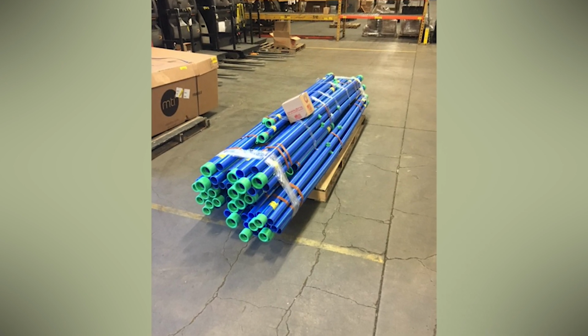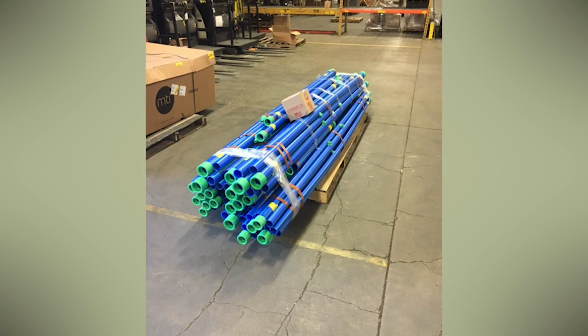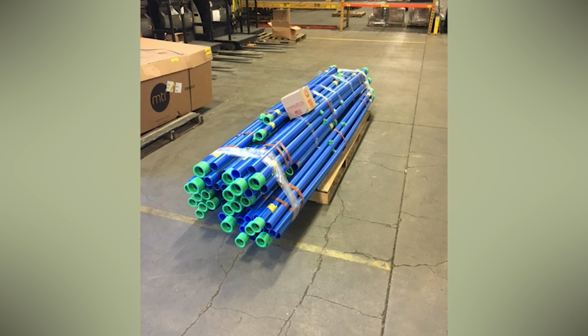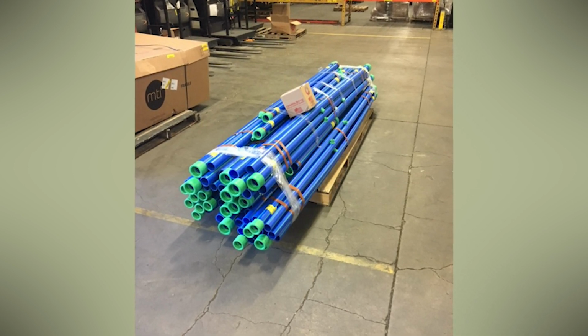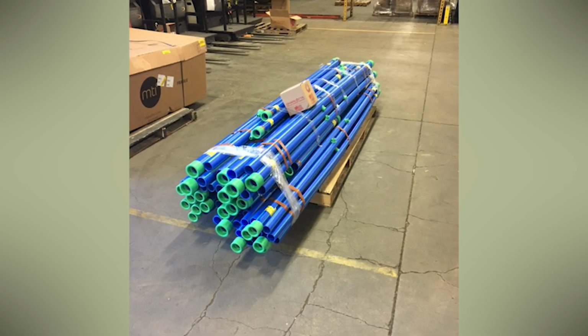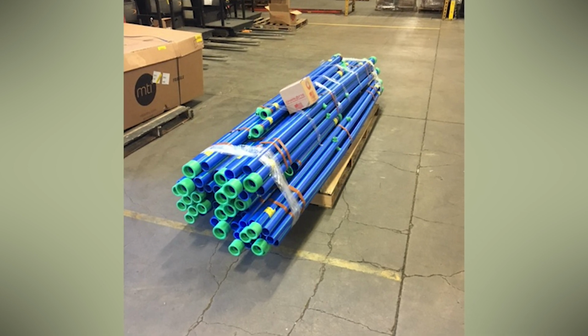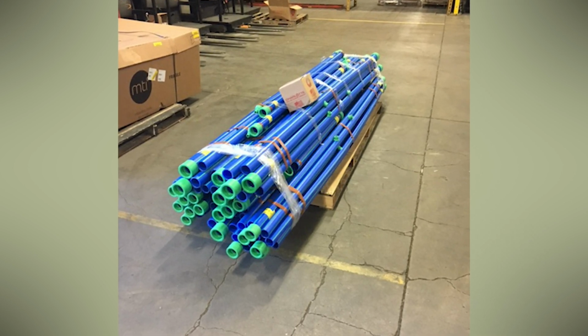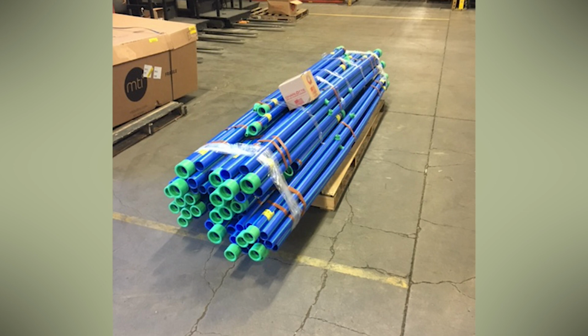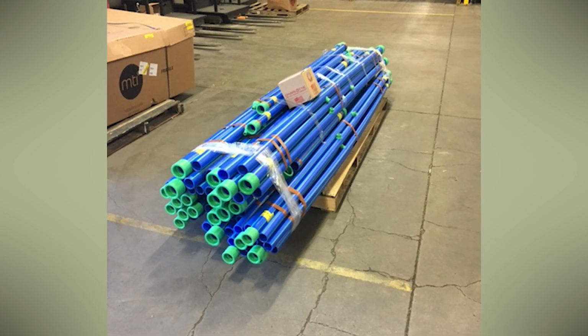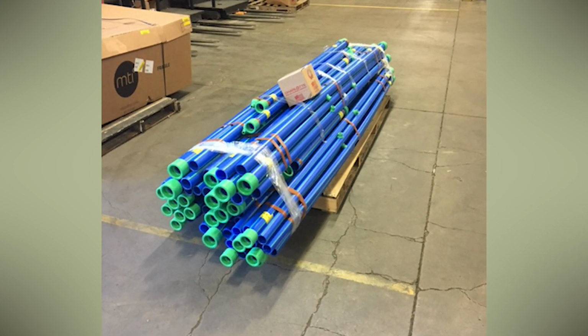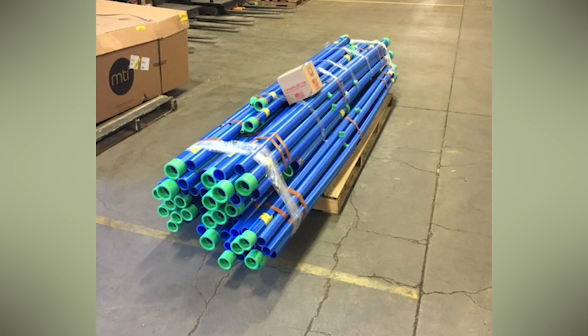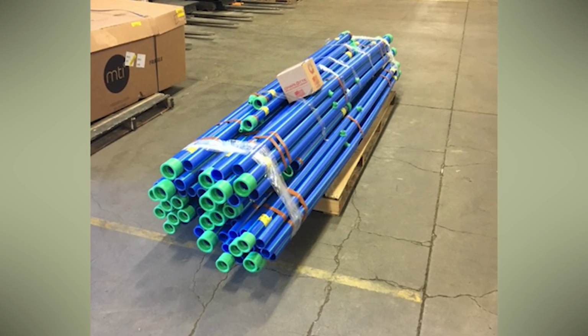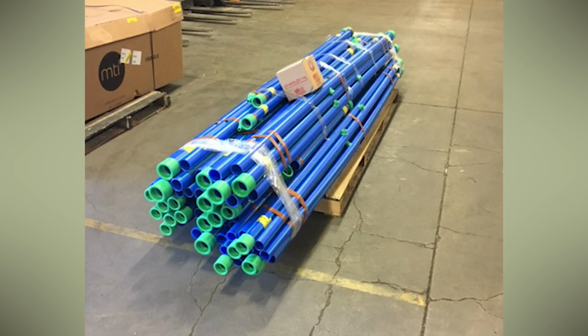Off-site fabrication saved about 4 to 5 days per riser, reducing the time to complete the project without adding cost. Ferguson had a better equipped shop and didn't require cost of freight. Plus, off-site fabrication allowed the contractor's personnel to spend their time working in the field. The light weight of PPR pipe was an added benefit. All the piping had to be taken up in elevators in 9-foot maximum sections. Even the 4-inch pipe could easily be handled by one person.